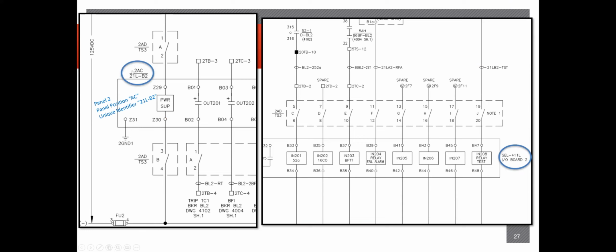The panel designation is usually this top two right here, and the panel position would be the AC. A unique identifier is something that differentiates from client to client. Usually they have a set standard, but in this case, I'm assuming they're identifying this as a line relay with their 21L, and B2 could be a backup relay, possibly. I'm not sure what client this is, but each client will have a different identifier, and it can be a little bit of a pain to differentiate them, especially if you're working on different projects here and there quite frequently.